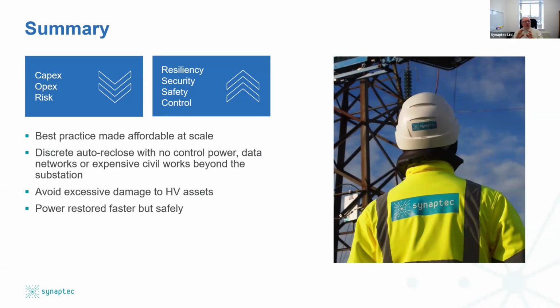So if you've got that sense of discrete auto reclose, and yet you can do it without the traditional cost of control power, data networks, and substation work and civil works, there's a big saving at a CapEx and an OpEx level. Clearly, that's also a risk reduction. It's also an outage reduction that comes through in your SAIDI and SAIFI numbers, which are critical. And it's a simple thing now to do and to deploy for a sensible cost that gives you that implementation of best protection practice in reality. So it really is about avoiding damage and restoration of power rapidly and safely.